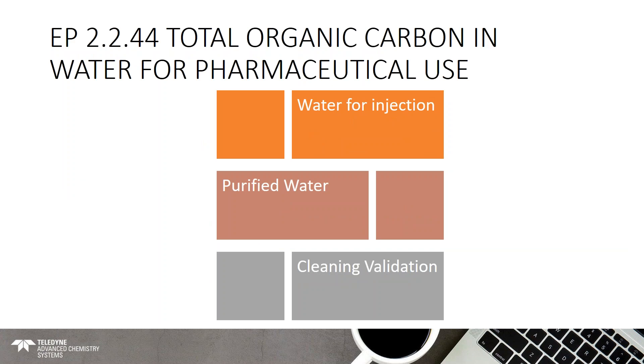EP 2.2.44 is entitled 'Total Organic Carbon in Water for Pharmaceutical Use.' Common pharmaceutical applications include water for injection — extremely pure water used for injections into veins, muscles, or under the skin — as well as purified water used for formulating pharmaceuticals or cleaning equipment. There is also cleaning validation: the FDA mandates cleaning validation of all equipment used to manufacture pharmaceuticals to prevent contamination, including cross-contamination between batches, foreign contamination like dust and bacteria, all of which can be detected through TOC analysis.